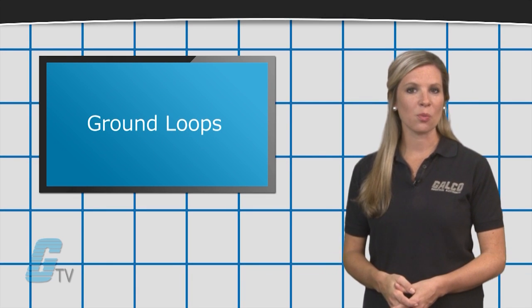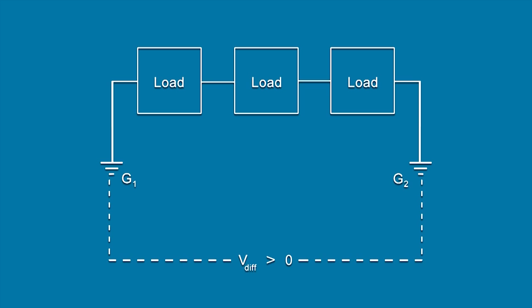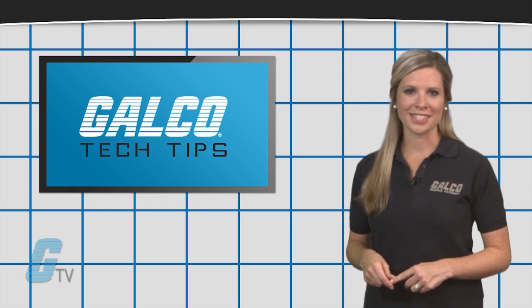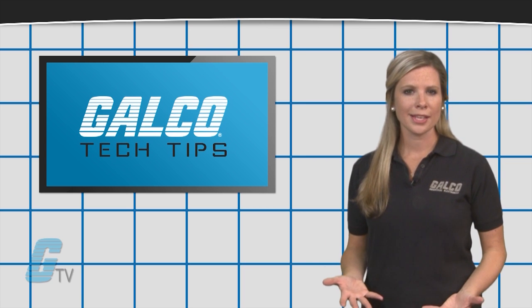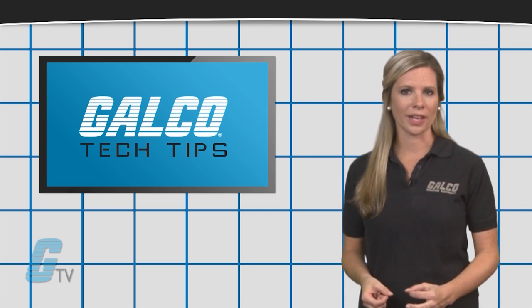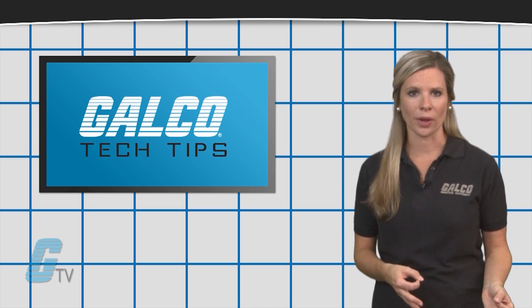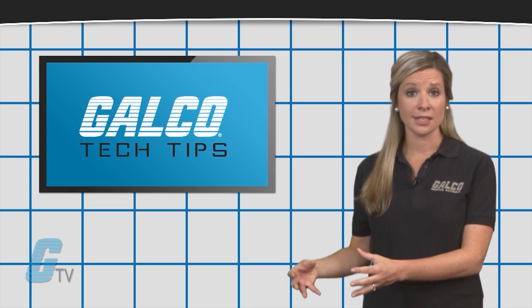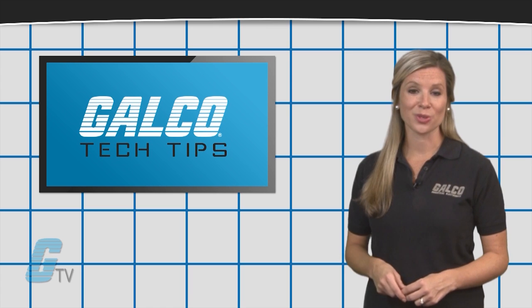Ground loops can occur when there are connections to two or more ground points from different potentials. When grounding devices that are connected in some way, they should be grounded at a single point and usually at a common point where the group of devices meet, such as in a bus bar or a drive.